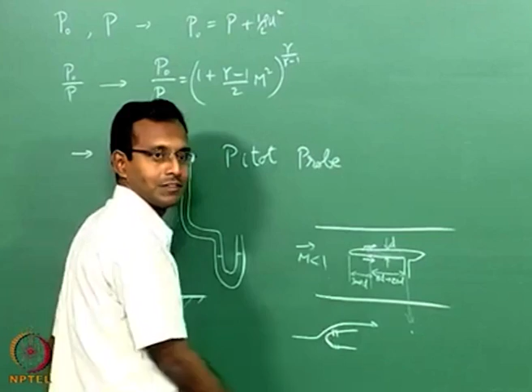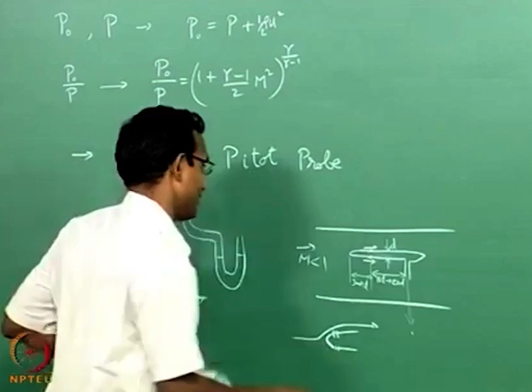If I go far away from here, it is going to become parallel. But still, if you think about it, this probe is blocking some area in my whole test section. Ideally, the area available for the flow has decreased. What we have to do is minimize this so that I am not intrusive. As much as possible, we have to make the D as small as possible. If I make the D small, the hole size, I have not marked the hole size, the hole size is 1/10 of D, typically they use. We will come back to that why next.